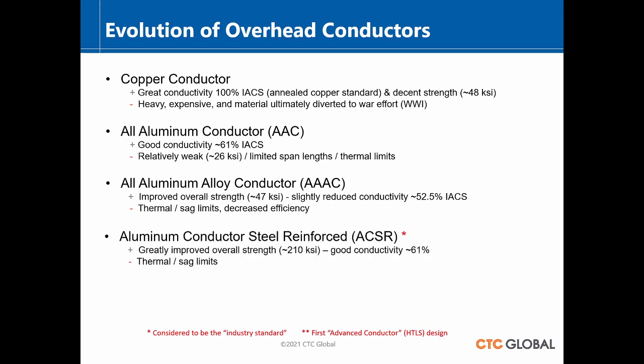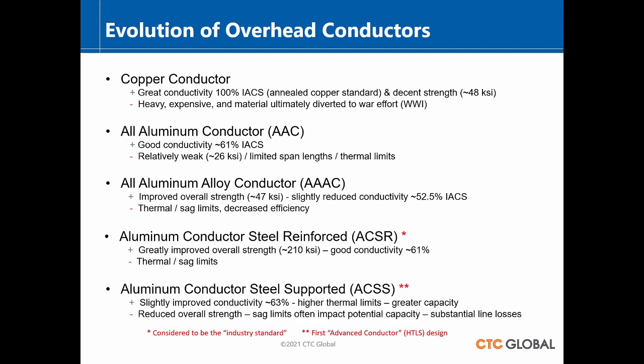By the time World War II came along, following the growth rate after the war, ACSR became the standard go-to. That product allowed good overall strength, could go quite a ways between towers, and had good conductivity, but they did have sag limits they had to face.